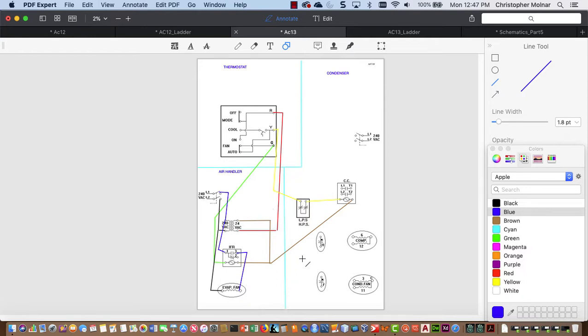Okay, we're going to do L1. Again, start there, run there. Okay, start is my higher ohms, run is my terminal with the dot if it's there. Sometimes it's just marked H and F for hermetic, which is my compressor. F is condenser fan.